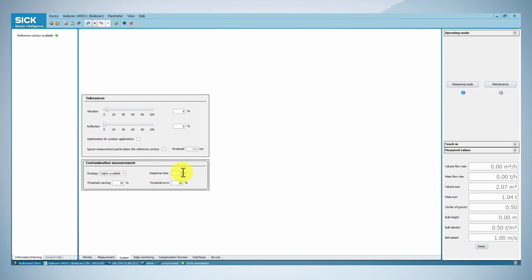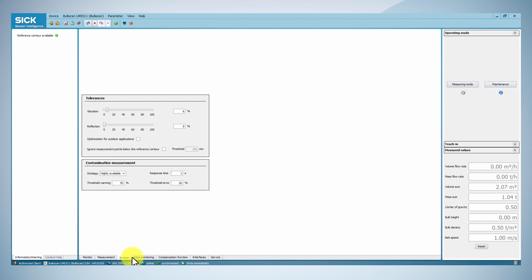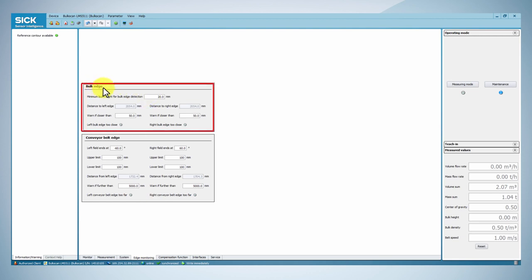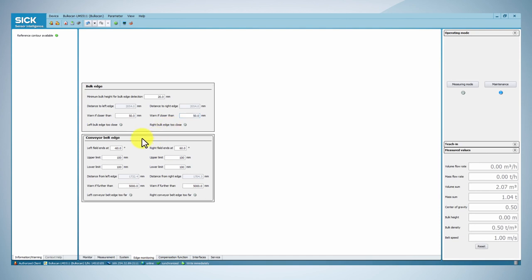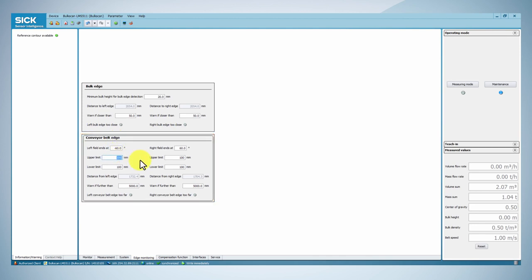If you wish to monitor the position of the bulk material on the conveyor belt, you can go to the bulk edge tab, set up warnings in order to prevent the material from falling out of the belt. Furthermore, you can monitor the position of the conveyor belt outside of the measurement area by setting up warnings. This can help to avoid damages due to the belt slipping or tilting.